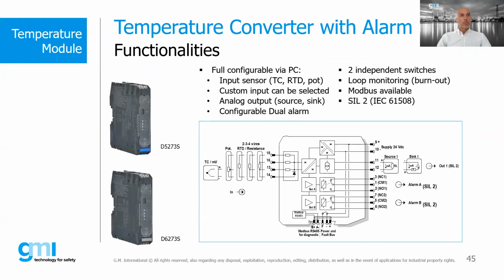We also have a unit with dual alarm. In this case, for temperature applications, one or two alarms can be set as a low alarm, high alarm, whatever is needed, with Modbus configuration, and also a Modbus interface.